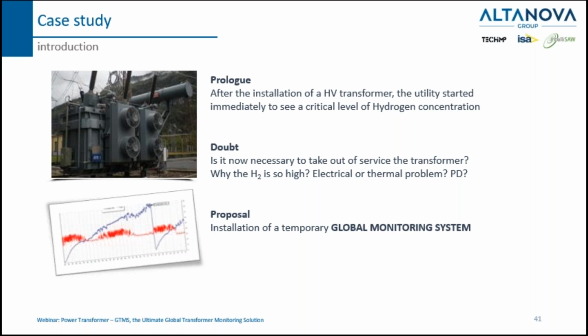Immediately after the installation of this new HV transformer, the utility started to see a high level of H2, so hydrogen concentration. Then the question was, is it necessary to take the transformer out of service, and in other terms, why is the H2 so high? The utility's concern was about the reasons for this behavior, an electrical or thermal problem.